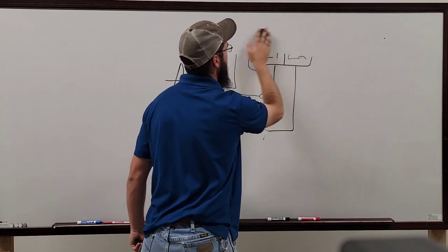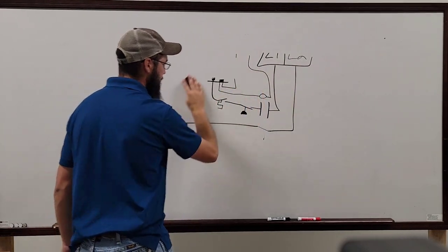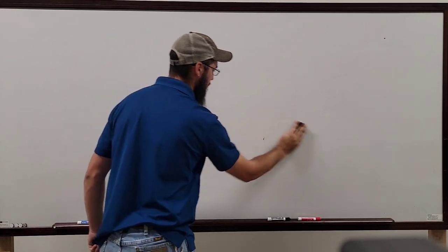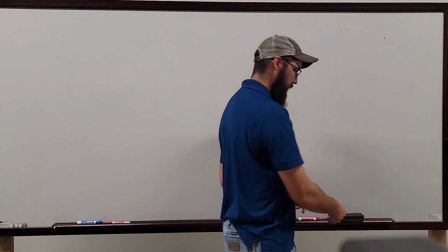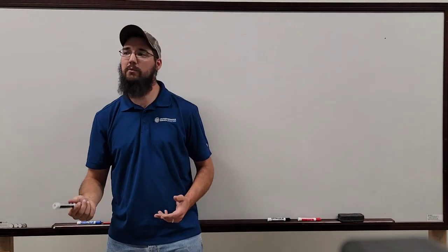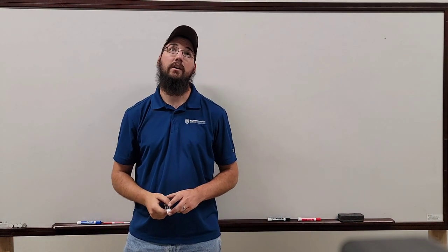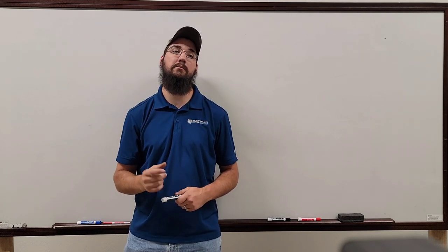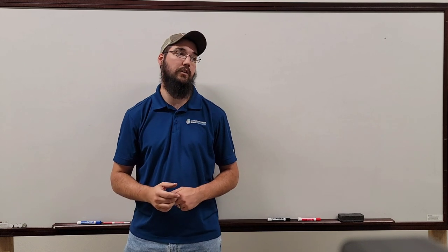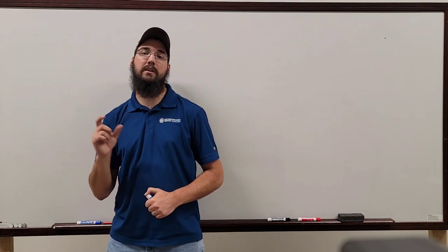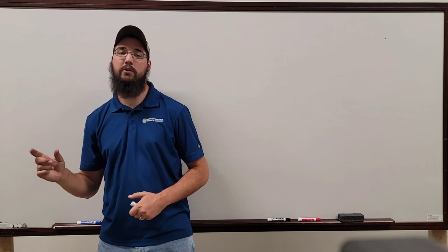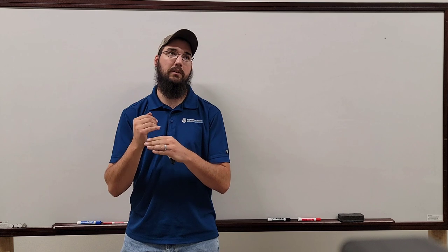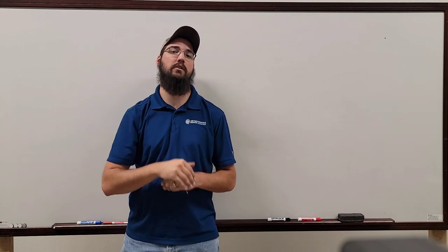Now you can use all this to also calculate CFM. That's not our primary function in this particular class. That's kind of more of an airflow thing. But if you take your BTUs and divide them by your temperature difference across the heater, multiplied by 1.08 as a coefficient, that gives you CFM.